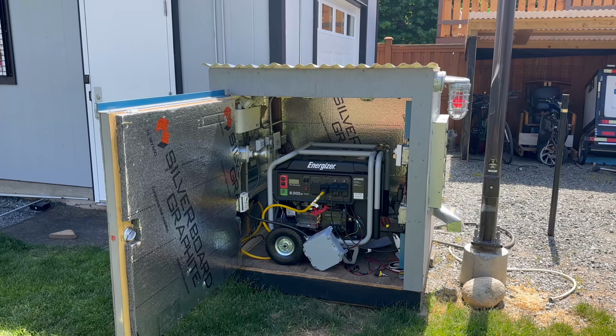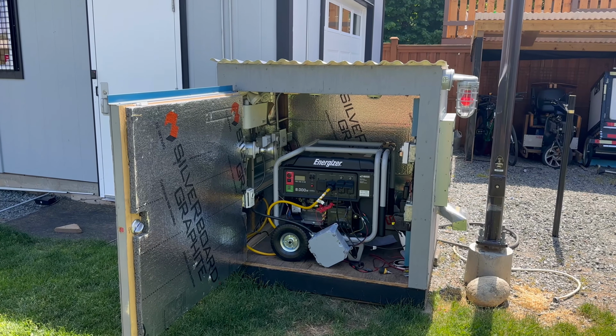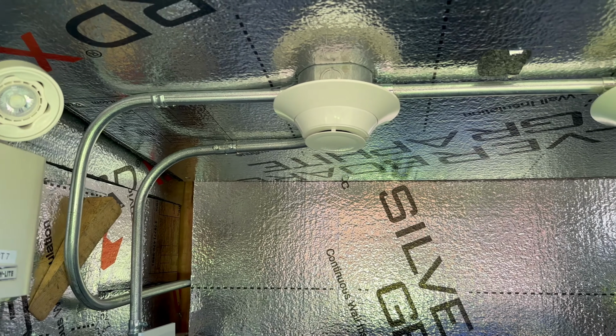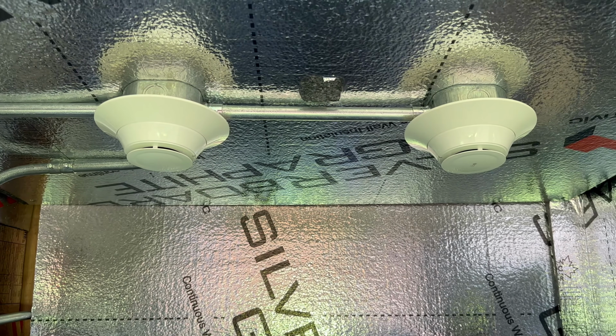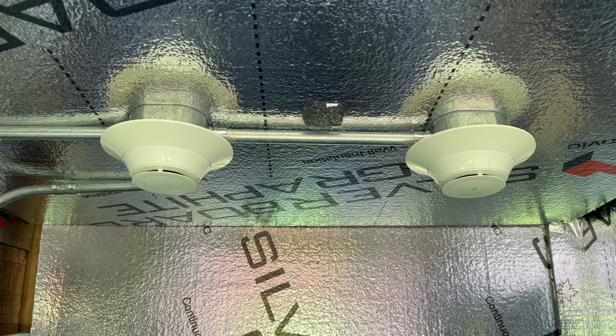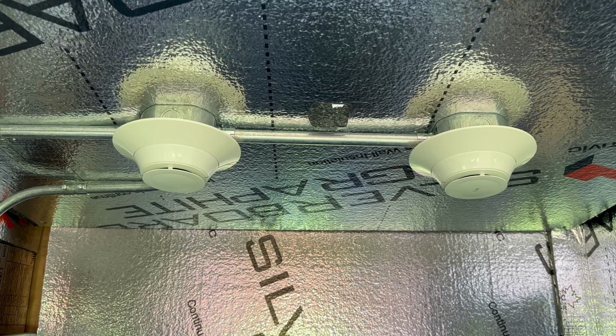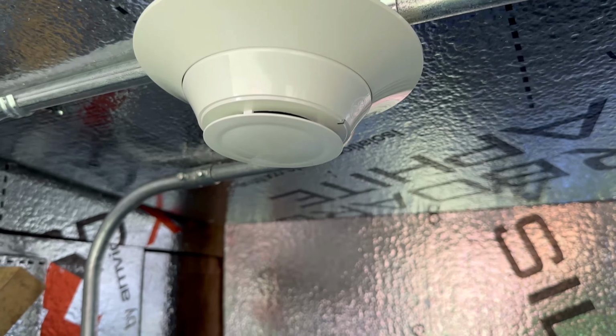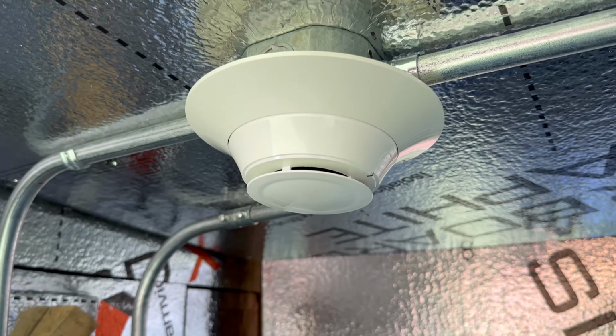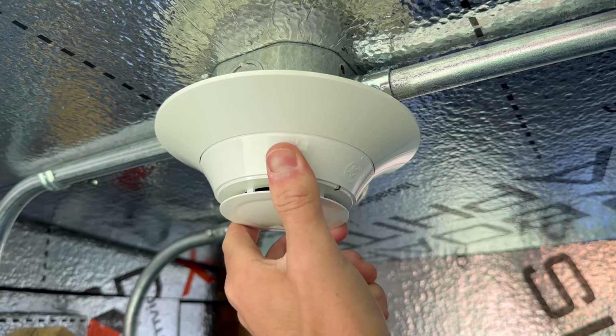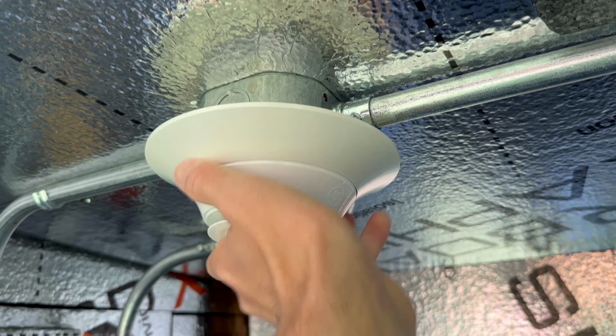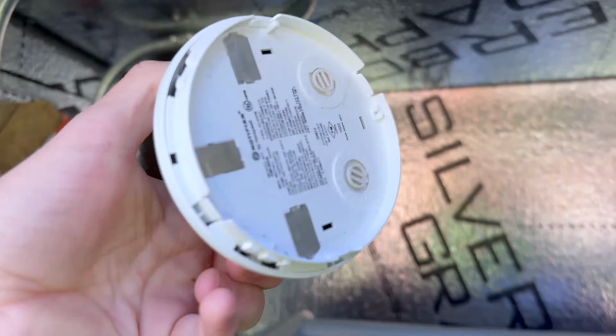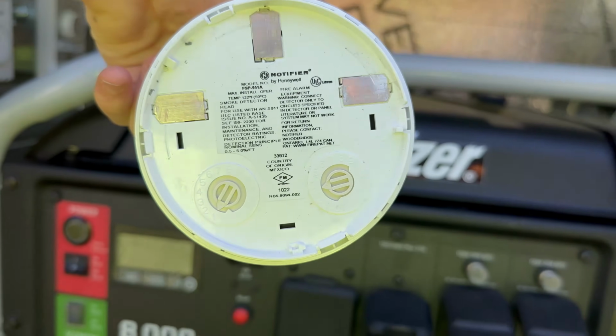Now let's talk about the safety systems that are put in place in this generator building. While we're still on the fire alarm subject, there are 2 components in here that are tied into the fire alarm system. We have a smoke detector and a heat detector. The smoke detector here is another addressable device where you actually set the device address on the back. I can take the device down. It will put the system into trouble. There is how you set the device address.